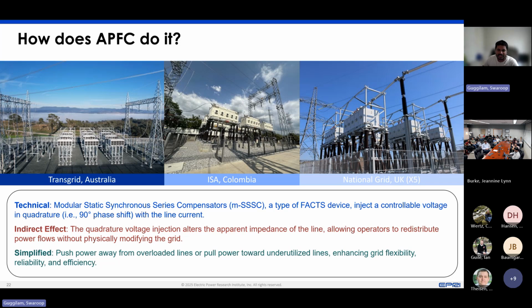This APFC device provides that flexibility and control. For instance, if one transmission line has reached its maximum capacity while another is only 50% utilized, you can install this device on either line and push power away to the other, so they're more equally utilized—allowing more overall transfer capability.